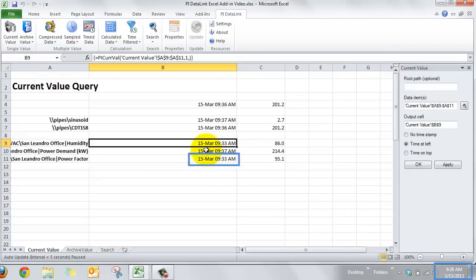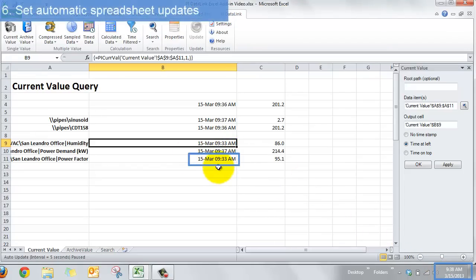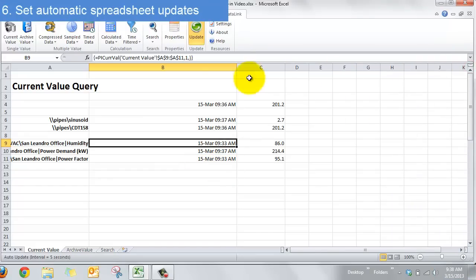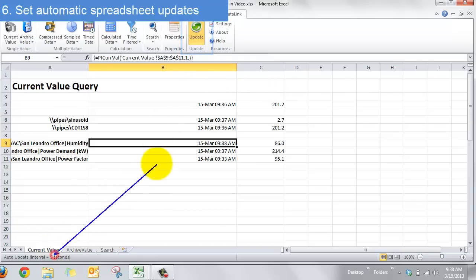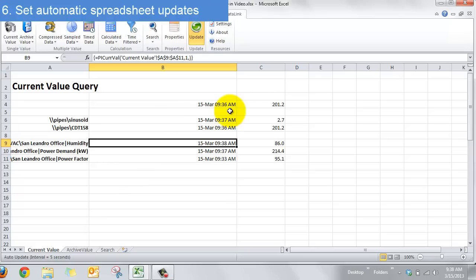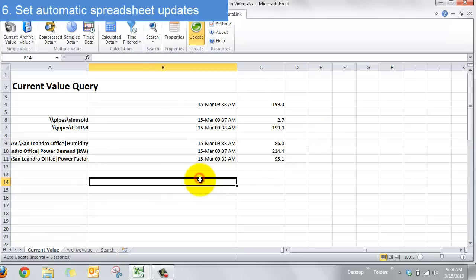If I want these to automatically update as time goes on I'm just going to need to close my wizard and then activate the update button up here. And you'll notice when you do that Excel will say auto update interval has activated. So this means every five seconds it will check if there's a new value. And when there is a new value it will put it out on the sheet.